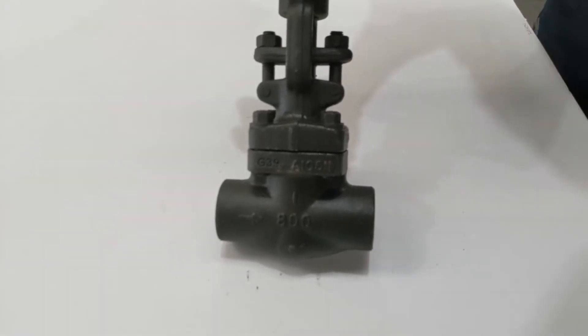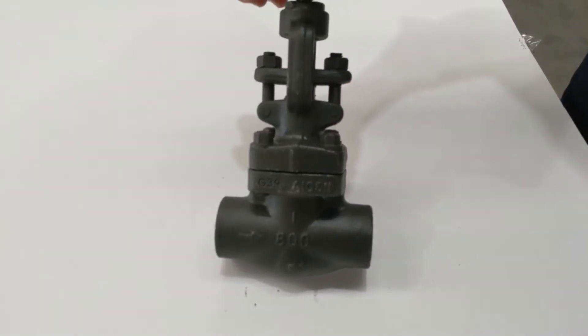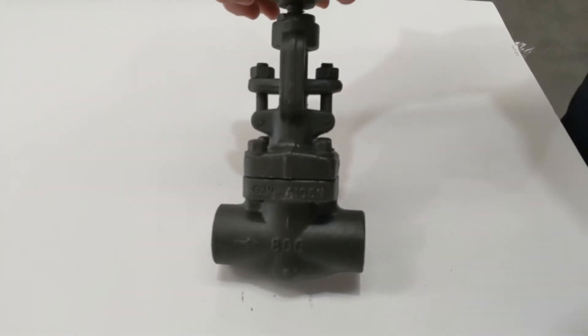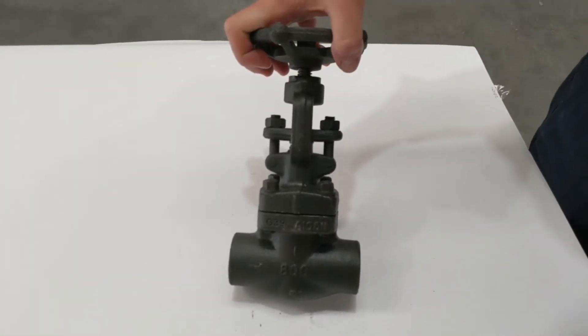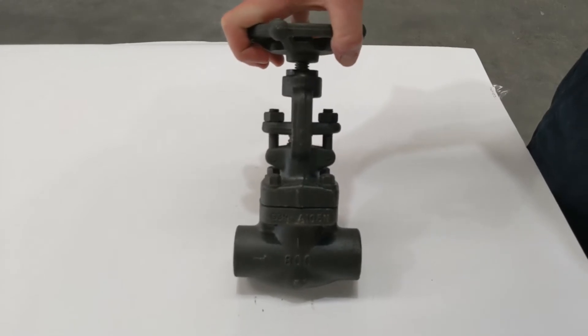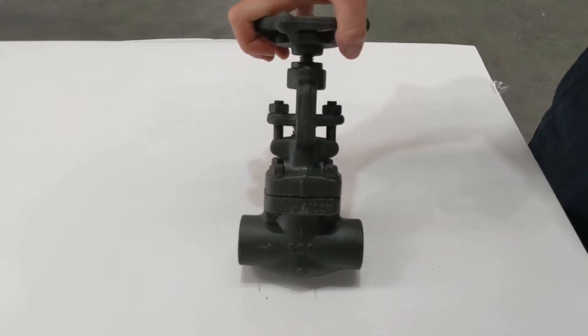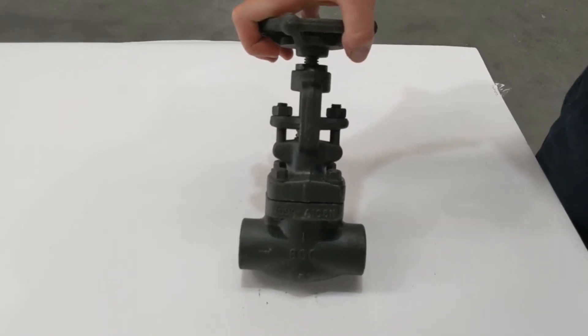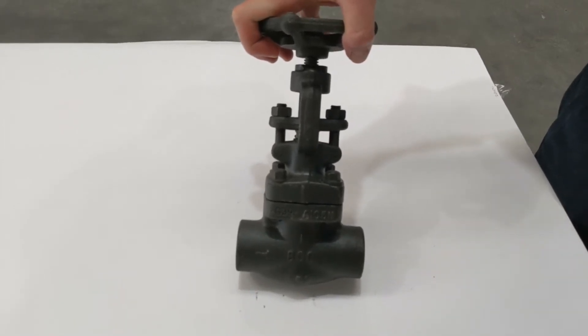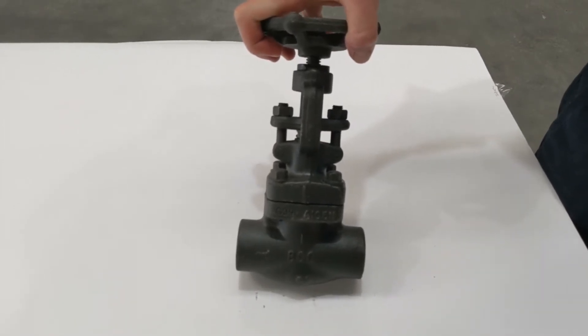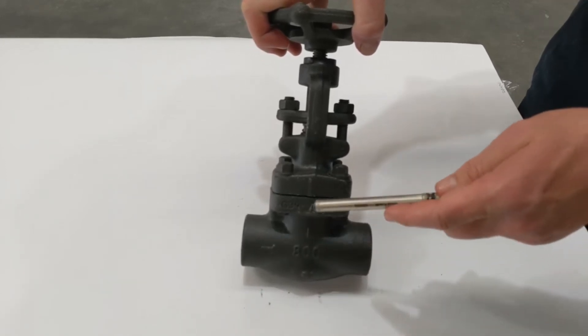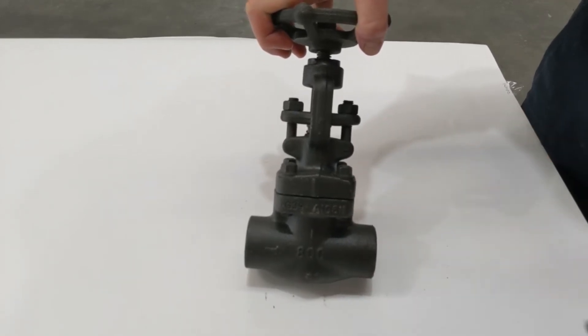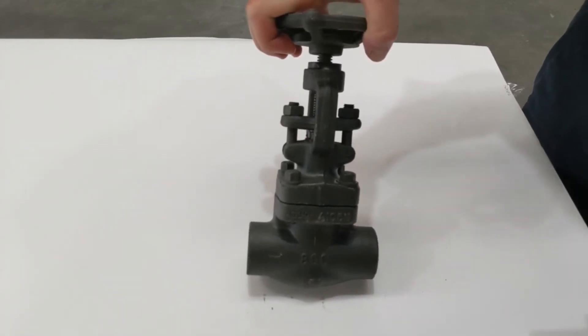Now the bottom of that globe is stellite reinforced. That's because it sits in the middle of the flow all the time, and if you had a medium like steam it's going to wear, so the stellite is a very hard surface.